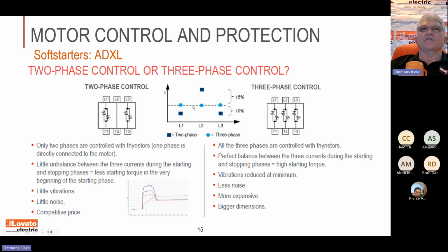And the diagram here they're trying to show you is on a high torque starting load, 3 SCRs are really what you want. A lot of these fans and mixers that just spin real easy, you can use the 2-phase control. But when you get into these big, heavy inertia grinders and stuff that got to start off under a load, yeah, you really need these 3 SCR type, 3 controlled outputs, I think we call them.